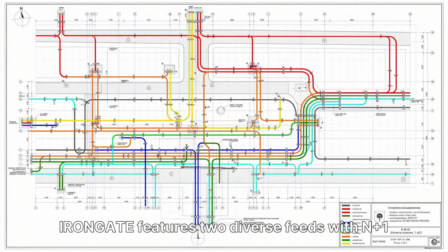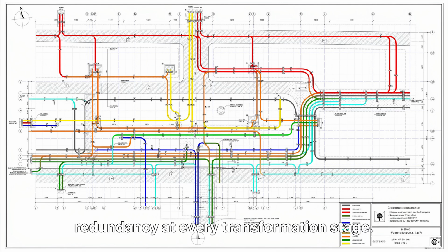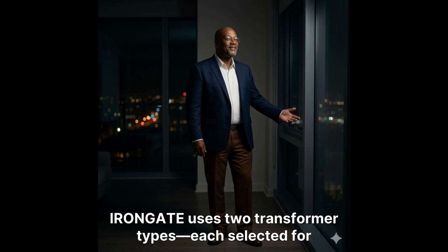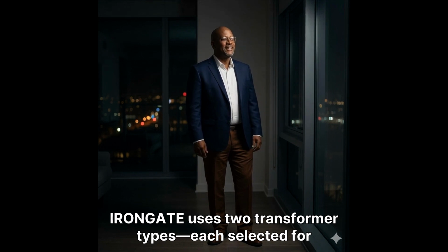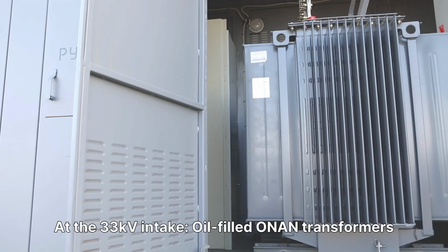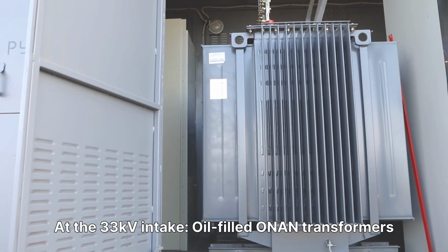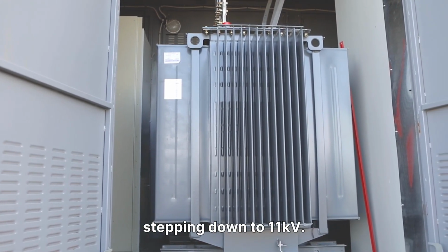From there, power flows to the UPS systems, generators, and critical cooling infrastructure. IRONGATE features two diverse feeds with N+1 redundancy at every transformation stage. IRONGATE uses two transformer types, each selected for its specific application. At the 33 kV intake, oil-filled ONAN transformers step down to 11 kV.